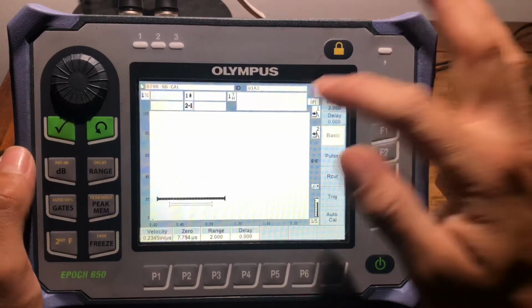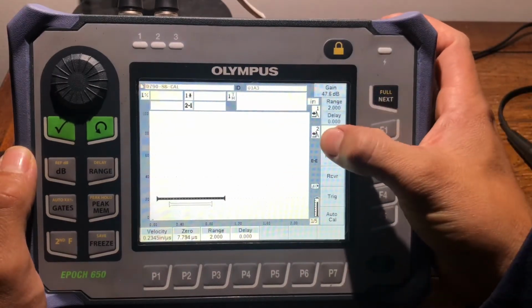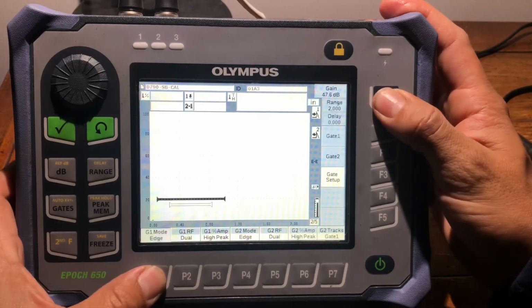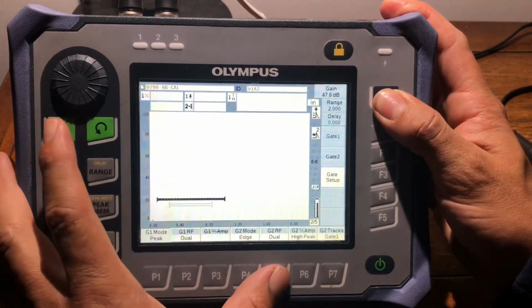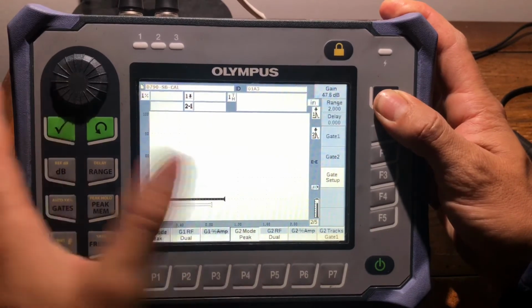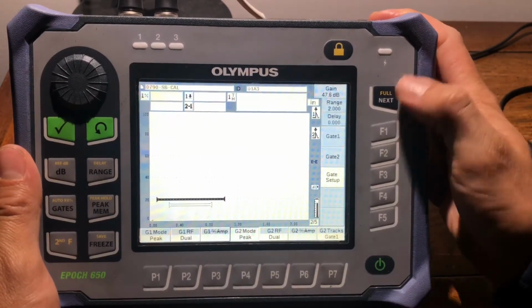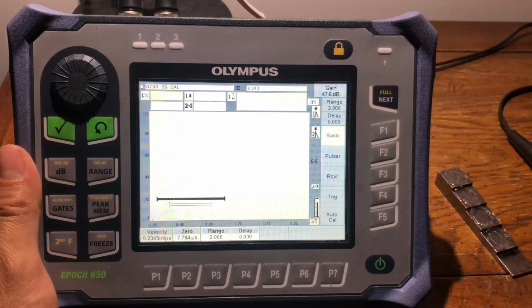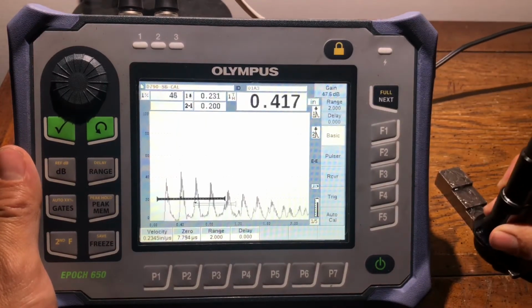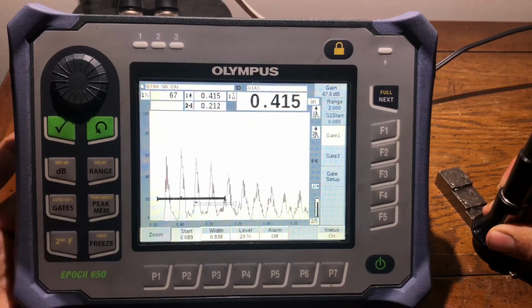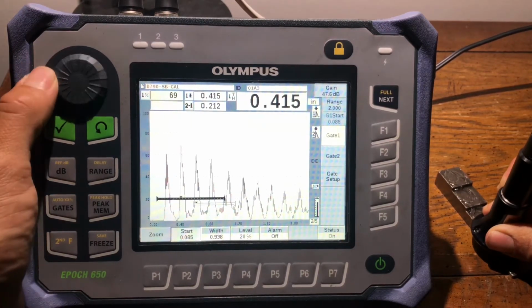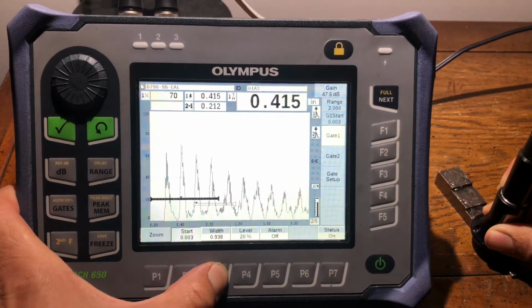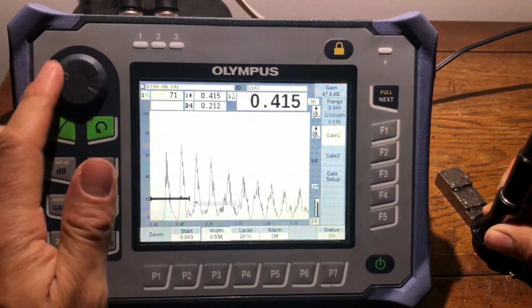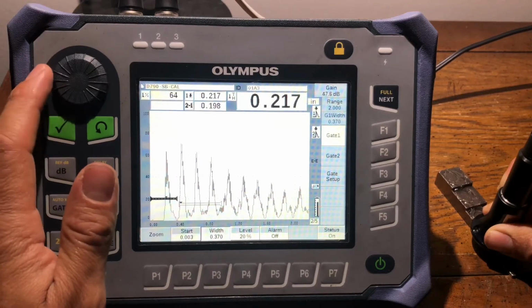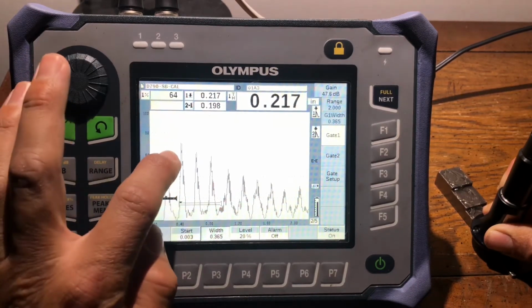Got edge to edge. So I am gonna save another calibration on the third file, and all I'm gonna do is change the edges of our peaks right here to peak, and that changes both of them, peak to peak. And we're gonna see how that affected our calibration. We should be off by a bit, so we're gonna fix our gates right into place. Now we're reading the highest peak, so I gotta make sure that our gates are in place. As you can see, now we're reading the highest peaks.